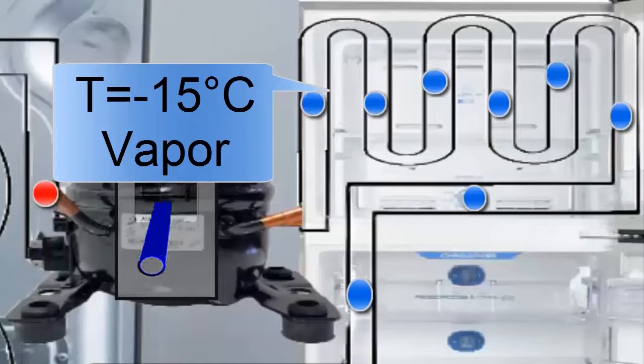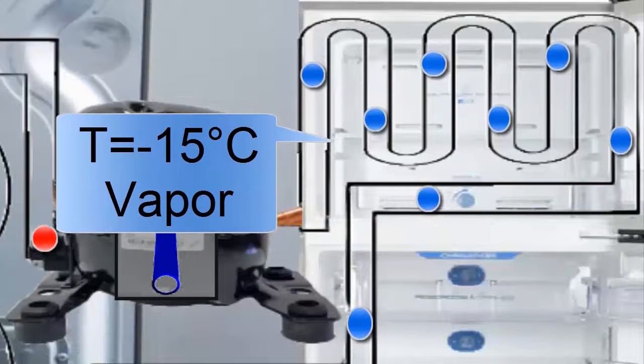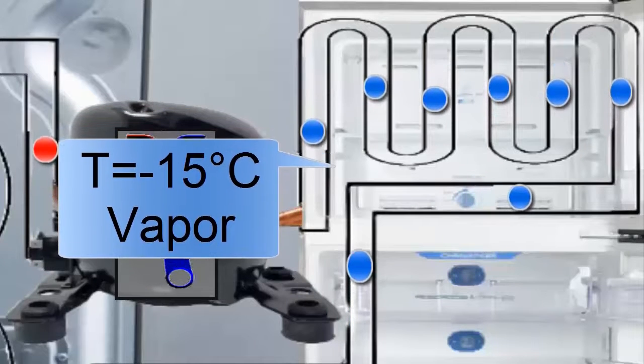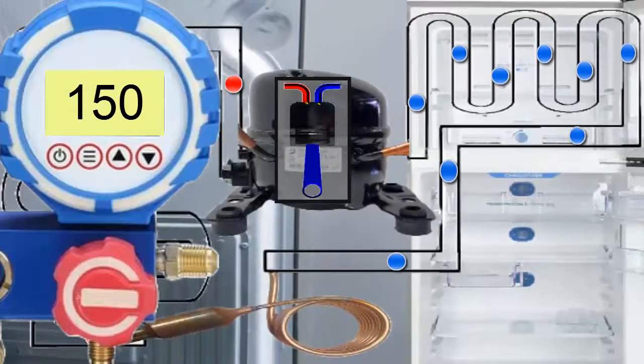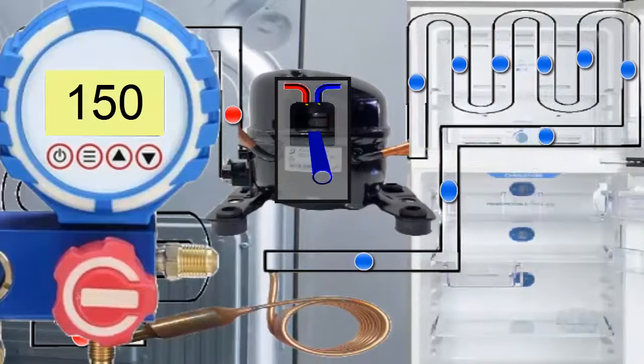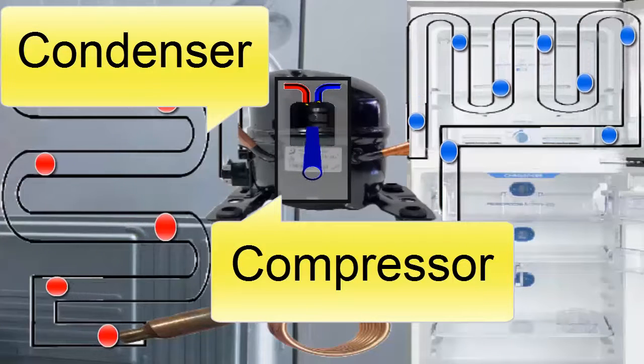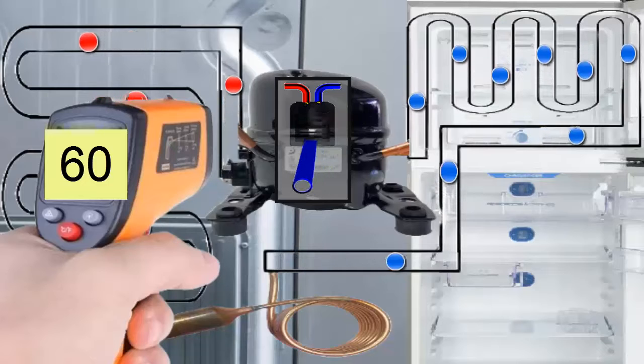The pressure and temperature of the refrigerant increase significantly in the compressor. The pressure of the R134A at the compressor outlet reaches a value close to 150 pounds per square inch. The temperature of the R134A at the compressor outlet can be around 60 degrees Celsius.